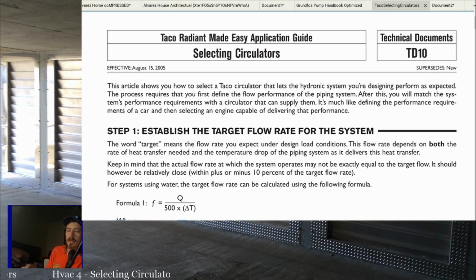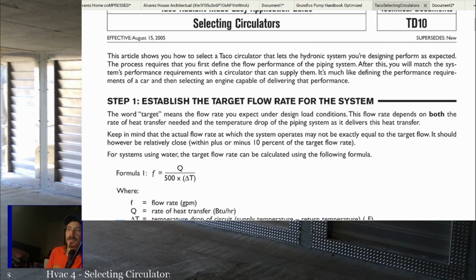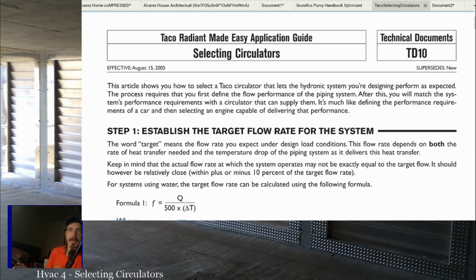It could be there are instances in which a baseboard's clogged up or a radiator's clogged up or something like that. But there are times I've found when the circulator just wasn't sized properly. So if you ever run into that situation, this is what I recommend as your point of reference for sizing a circulator pump in a boiler system, or for that matter, anything where you need a circulator.